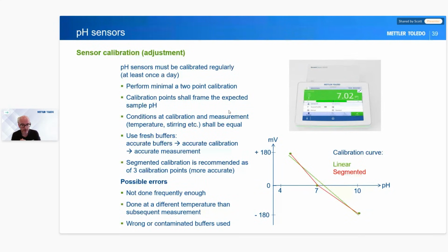The more calibration points we've got and the more segmented it is, the more accurate our measurements are going to be. But we should have at least 2, if not 3 points. And yet again, we should try to make sure that we calibrate at the same temperature we're taking our readings. That will help with measurement uncertainty. If we calibrate hot, we measure hot; if we calibrate cold, we measure cold; if we do it at room temperature, then we calibrate at room temperature. We should always use fresh buffers, so we need to make sure we're using accurate calibration buffers for accurate measurements. The possible errors there are not doing it frequently enough, so make sure you're doing it at least once a day, doing it at the right temperatures, and making sure you've got the correct buffers.